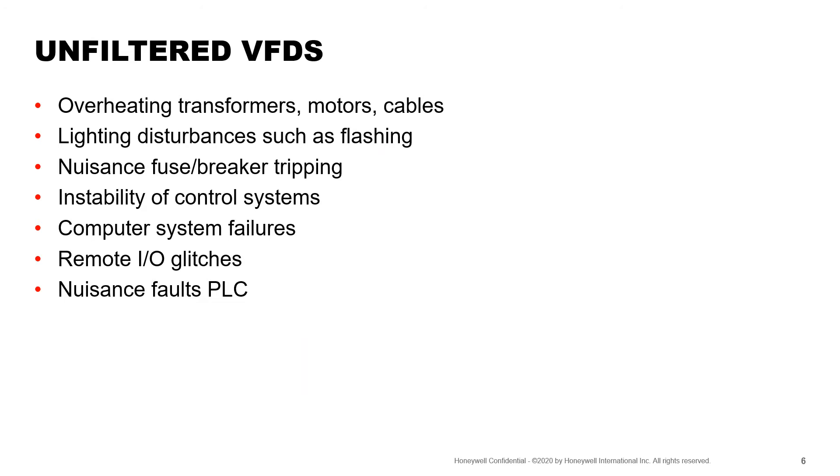VFDs that are not filtered can create electrical noise back into the electric network of the building or even out onto the grid. This noise is called harmonic distortion and can overheat transformers, motors, and cause breakers to trip or microprocessors to lock up. Honeywell's smart VFD drives have filters to minimize harmonic distortion.